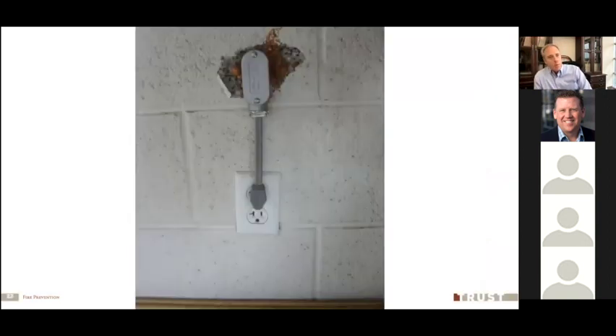Also, this temporary wiring, lots of times we see some pretty creative ways of getting electricity to where we need it. And this actually is maybe one of the better ones I've seen, where they actually did use some conduit instead of just running the cord through the wall. But what is this really rated for? When we have these home built electrical solutions, we may not be able to be certain that that is going to protect against an overload of that cord or the wiring that we've done there. And obviously this cord on here is subject to damage because it doesn't have, at least on that last part, that protection in a conduit.